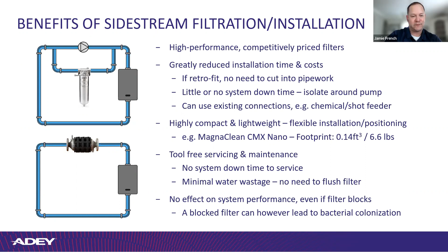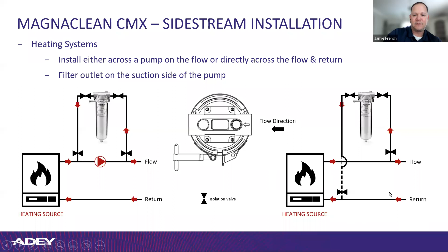Here's another picture, a bit more in depth, showing where to install this, with the filter outlet on the suction side of the pump. So you're going across it, creating that differential pressure and forcing a portion of this water to go through each time it goes through the pump. The other option is to go on the flow and the return, because you're still getting differential pressure through there. So these are some options for side streaming.